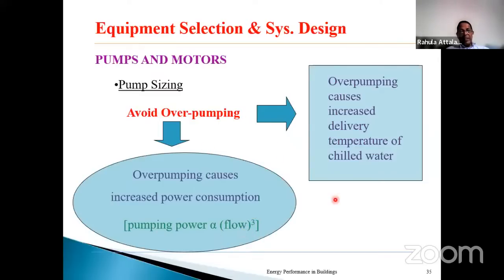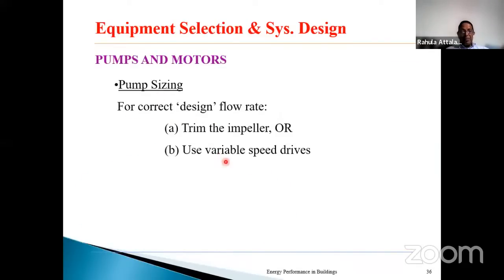Try to avoid oversized pumping. If you have oversized pumping, it will cause unnecessary heating of the chilled water, and also higher flow rates will make the pumping power unnecessarily high, to the power 3. So it is very important to do the sizing properly, and to make sure that if flow variation is needed, it is manipulated properly to get the advantage of the power. The capacity can be adjusted by trimming the impeller, which is the simplest but not the best method, or by using a variable speed drive.